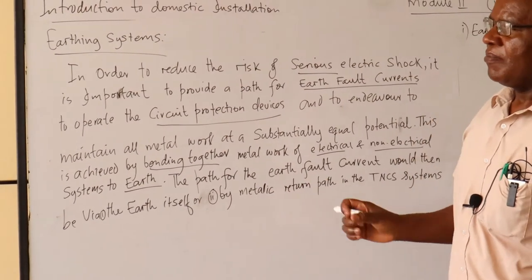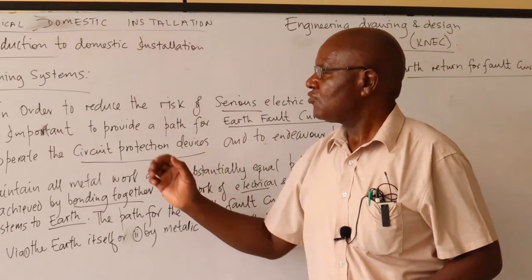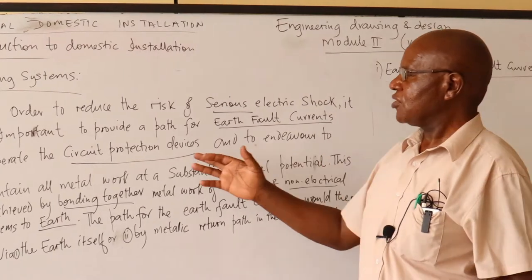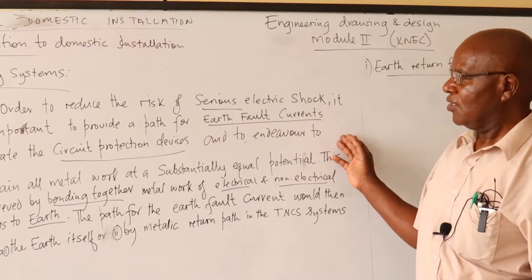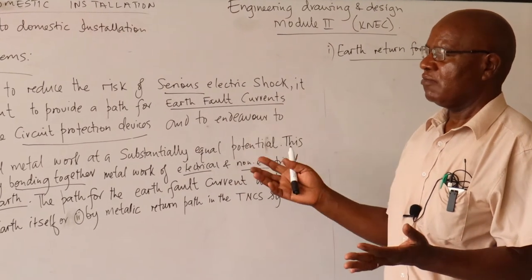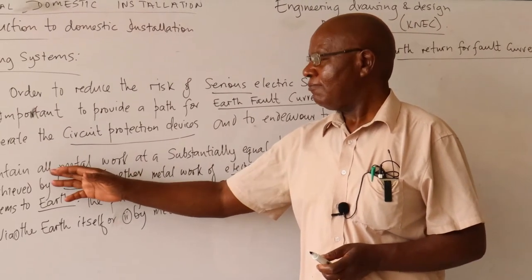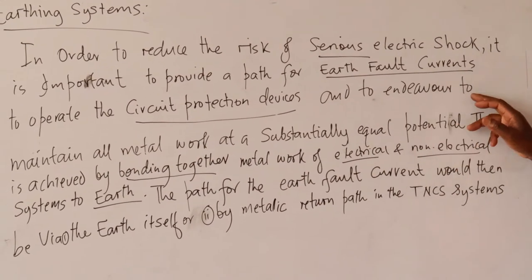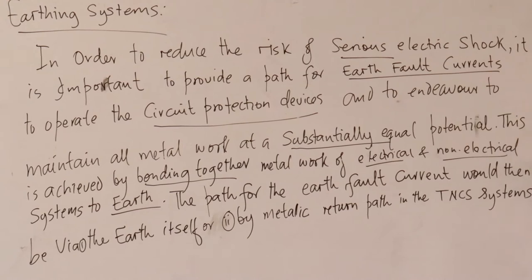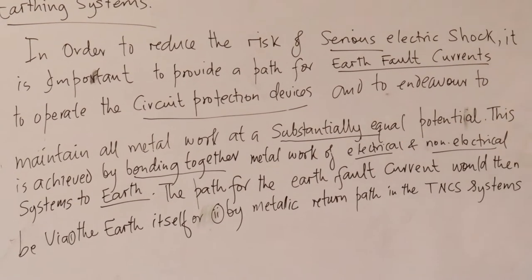Earthing is one means of providing protection in electrical installations. The key thing is that in order to reduce the risk of serious electric shock, it is important to provide a path for earth fault currents to operate the circuit protection devices — the fuses or circuit breakers — and also to endeavor to maintain all metalwork at a substantially equal potential. If you have metalwork at substantially equal potential, if you touch one area and another, the chances of getting a shock are minimum.